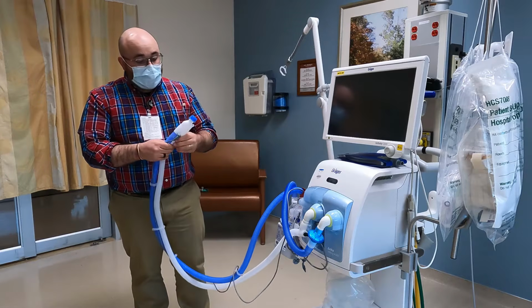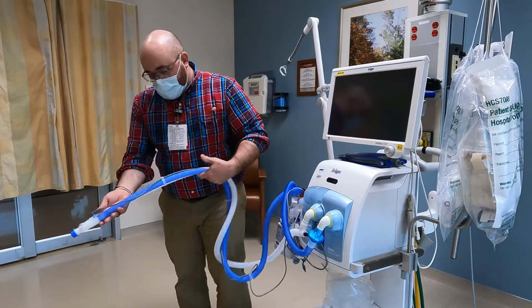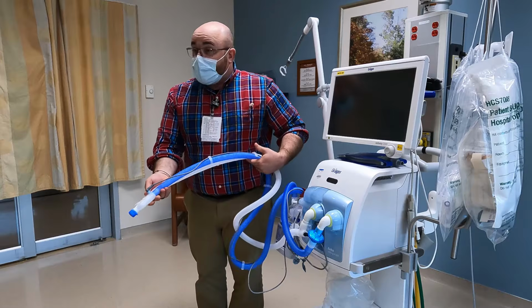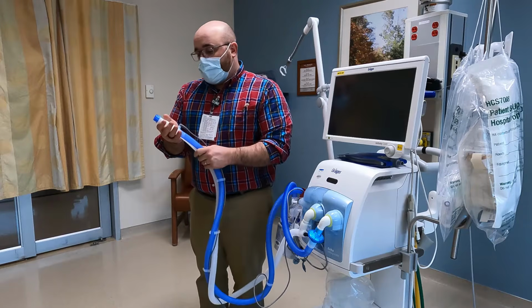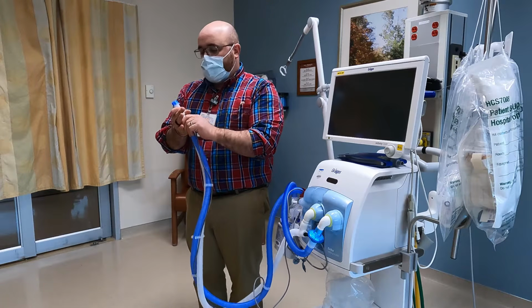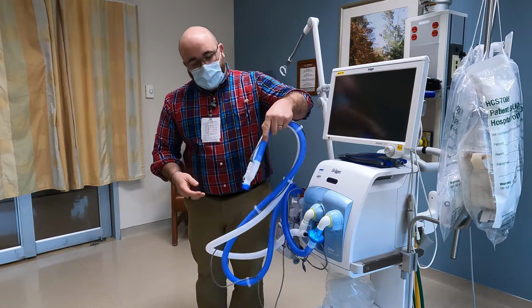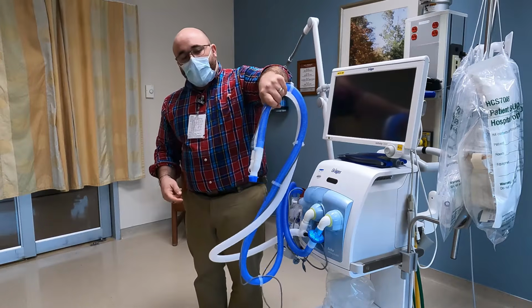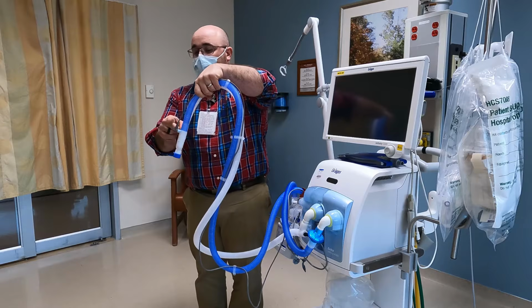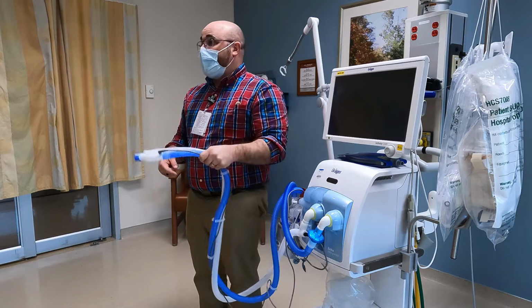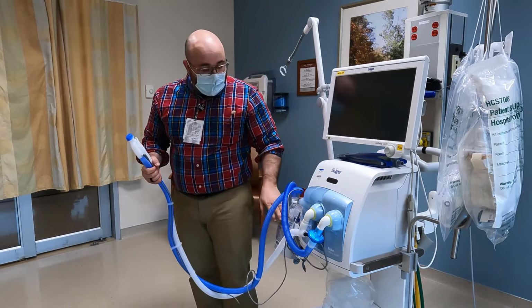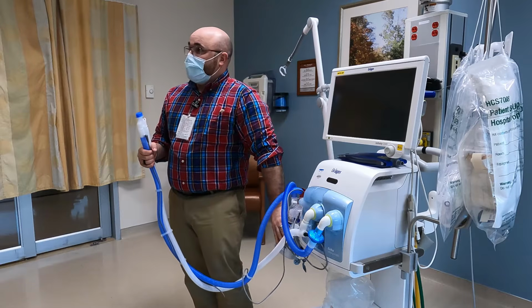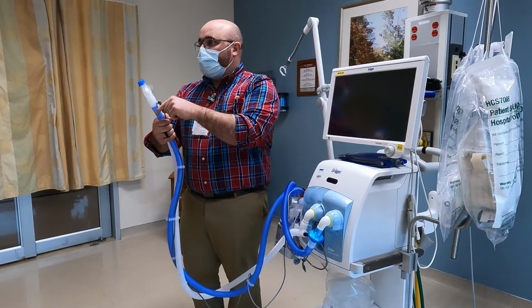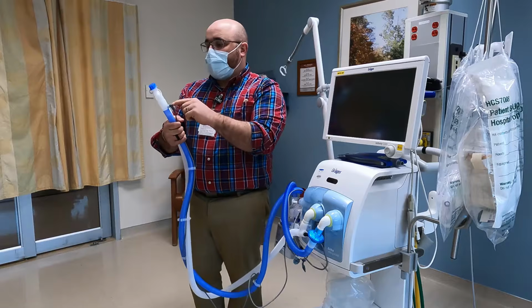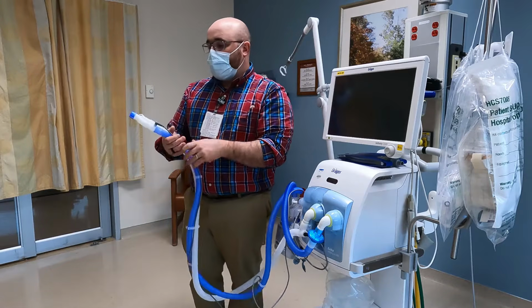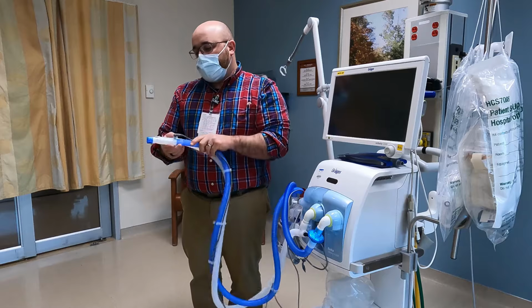So the expiratory side, as you can see, when it goes to the patient, if you're ever looking at a circuit, this is a good quiz for later on. They should put this on some kind of nursing test, but they don't. So if you're looking at a circuit like this, you always know whatever side the heater probe is on is the inspiratory side, because it's like 45 degrees Celsius here. We want to make sure it's 37 here. So it changes its temperature to get 37 here, because we don't want hot or cold air. So wherever you see this, that's the inspiratory side.